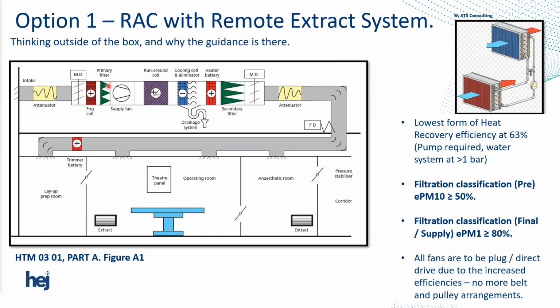And then working left to right, like I've said, we look at the supply air handling unit that sits in the middle. We've got the supply fan here. This is on negative pressure, that's under positive pressure. So as we move air this way, everything this side of the fan is under positive pressure. The runaround coil works like this. We have a coil that sits in the supply system and a coil that sits in the extract system. A fluid moves between the two, and a pump pumps that fluid round. And basically, obviously, we've got energy to run the pump. There's losses in the system to push the fluid around, so it's not ideal.